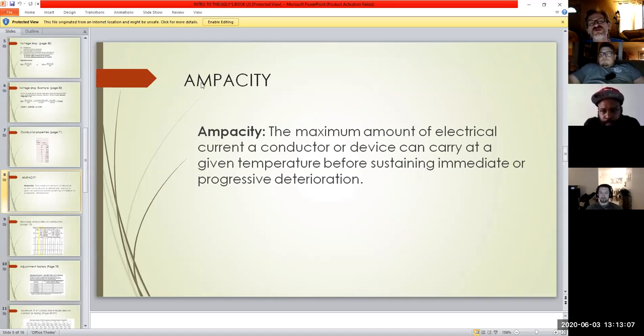And so that's when we run across this term, that's what they mean, ampacity. It's like I have the capability of running 30 amps or 20 amps or 15 amps, depending on my breaker size. And it always comes down to the weakest link in the line. You got your circuit breaker, your wire, and then your device. It would depend on what it is, but in a lot of cases, the weakest link is your circuit breaker, because it's saying this is how much you're going to deliver, and I've got everything else sized accordingly. That's what they mean by ampacity, and that's our new term of the day.